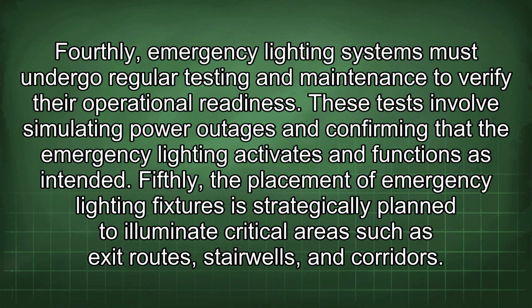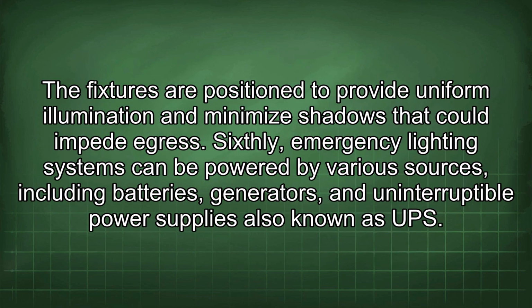Fourthly, emergency lighting systems must undergo regular testing and maintenance to verify their operational readiness. These tests involve simulating power outages and confirming that the emergency lighting activates and functions as intended. Fifthly, the placement of emergency lighting fixtures is strategically planned to illuminate critical areas such as exit routes, stairwells, and corridors. The fixtures are positioned to provide uniform illumination and minimize shadows that could impede egress.